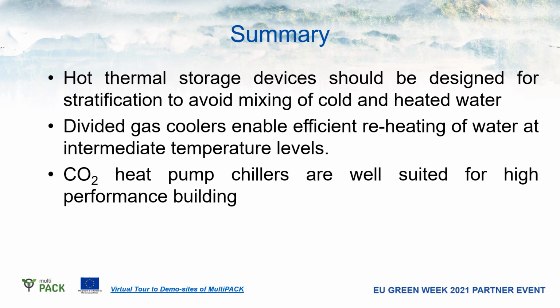In summary, the hot thermal storage devices should be designed for stratification to avoid mixing. It's very, very important with heat pumps. We need divided gas coolers to enable an efficient reheating of the water. And in conclusion, these heat pump chillers are well suited for high performance buildings in the future.